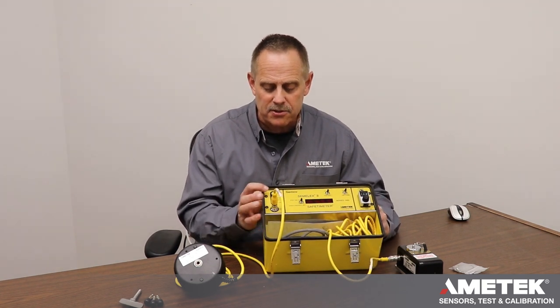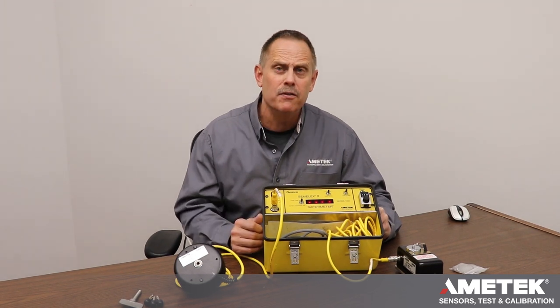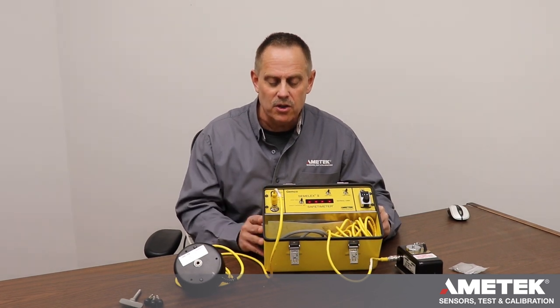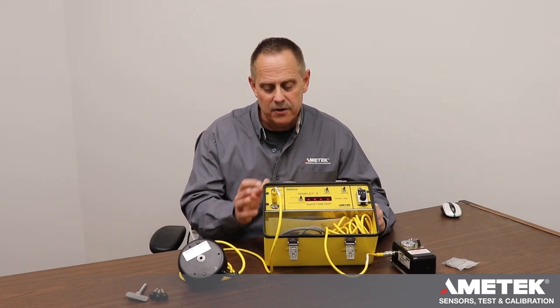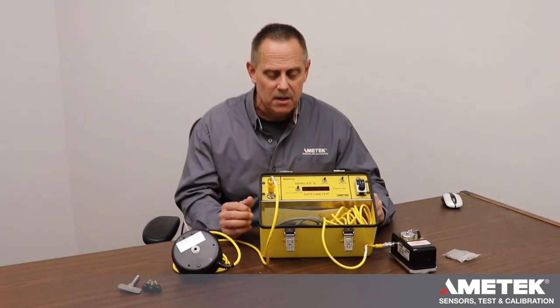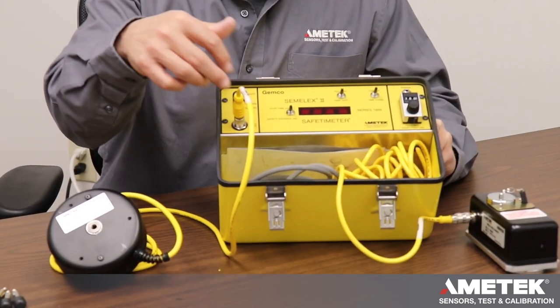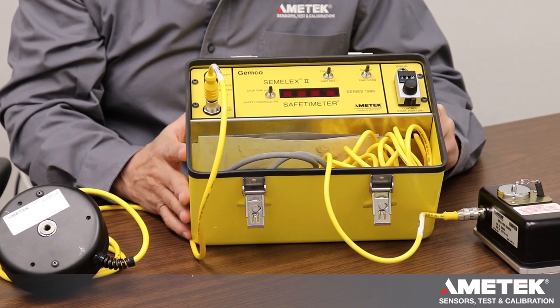Looking at the front panel: it's battery operated, so there's an on/off switch right here. You turn it on and it stays on for a few minutes. If you don't shut it off, it'll automatically shut itself back off. There's an indicator LED right here that will tell you when the battery is going low and needs to be charged. There are two connectors on here — one to connect the autotach, and the other to connect the position velocity transducer.